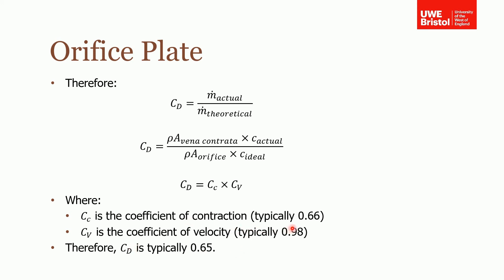However we need to include this additional coefficient which is the coefficient of contraction, which is due to these changes in area. So it's the vena contracta area divided by the orifice area and that's typically around 0.66 for an orifice plate.